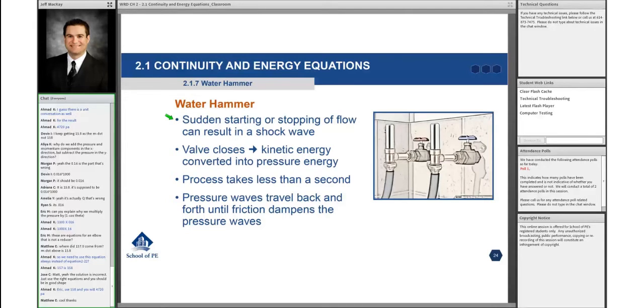can result in a shock wave - it's a pressure shock wave which is called water hammer. So for example, when you open up a valve and let water flow through the system, then suddenly close it, what happens to all of that kinetic energy when you suddenly close the valve and stop flow? What happens to all that kinetic energy? It has to convert to pressure energy, right?